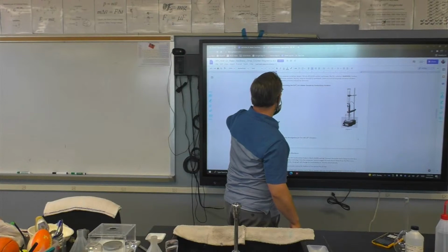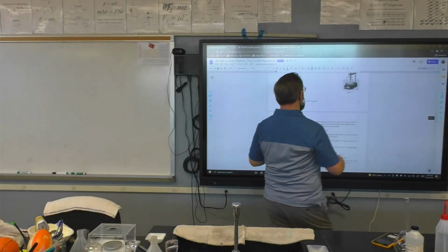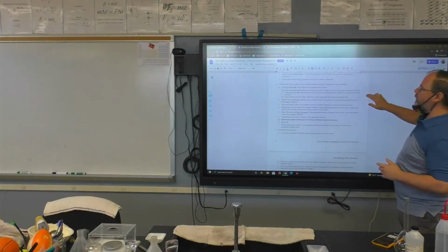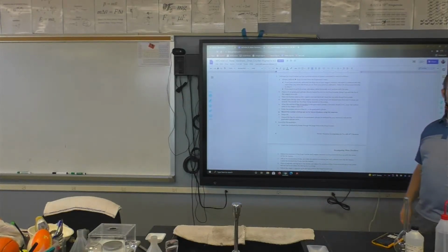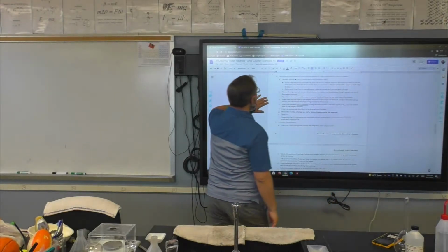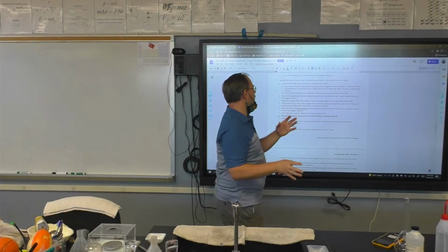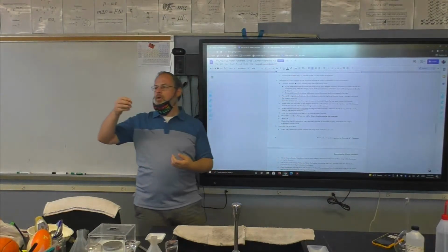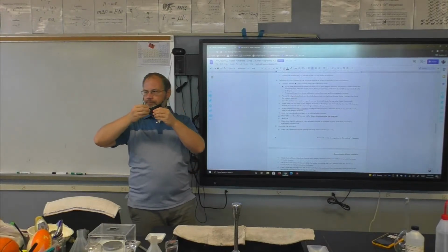Okay. So I talked about yesterday how to calibrate our drop counter, and as long as our solutions are fairly dilute, the number of drops per milliliter is going to be pretty much the same. So the first thing we need to do is plug everything in, get all the electronics ready to go, and then choose calibrate drop counter, and you're going to open the burette.